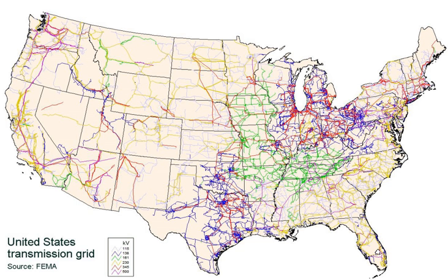All units to be connected to a grid should have the same droop setting, so that all plants respond in the same way to the instantaneous changes in frequency without depending on outside communication. Next to the inertia given by the parallel operation of synchronous generators, the frequency speed droop is the primary instantaneous parameter in control of an individual power plant's power output (kW).